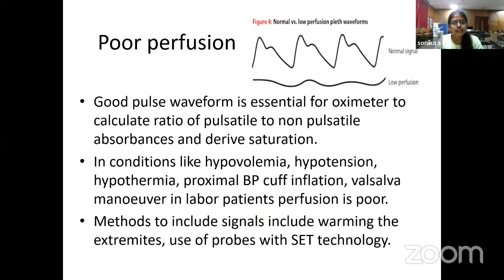As we all know, we use the operating principle of plethysmography in the pulse oximeter. So a good pulse waveform is essential for the oximeter to calculate the ratio of pulsatile to non-pulsatile absorbance and derive saturation. As we can see in the diagram, this is the normal signal, and in low perfusion we get low amplitude waveforms. In conditions like hypovolemia, hypotension, hypothermia, proximal BP cuff inflation, and also Valsalva maneuver in a labor patient, there can be poor perfusion. To minimize this, we can warm the extremities, place the BP cuff on the different hand, and also use probes with the SET technology.